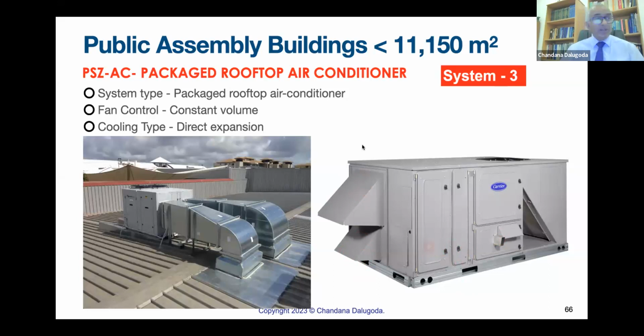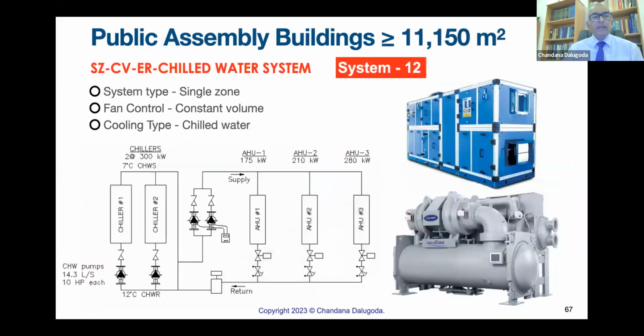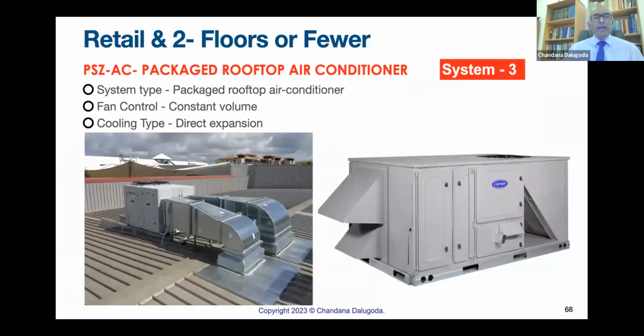The other advantage, this has an economizer built in. If the outdoor temperature drops below 24 degrees C, this will take care of bringing in outdoor air to cool the building. Probably night purge, we are just touching on that later. Public assembly buildings larger than 11,000, we are supposed to use single zone, constant volume air handling units, with chilled water cooling. See how nice. Again, retail, that is shops, and small offices, rooftop package.